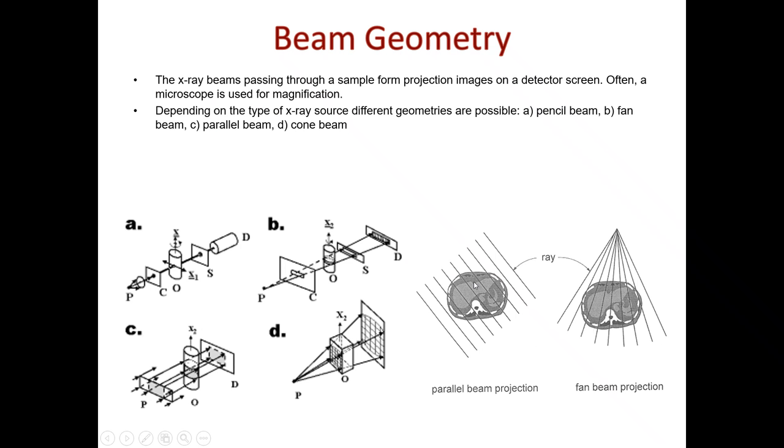All right. So geometry in this reconstruction is important. How do your beams interact with the object? So this is a parallel beam, okay? But I have to have a source that is emitting a parallel beam, right?